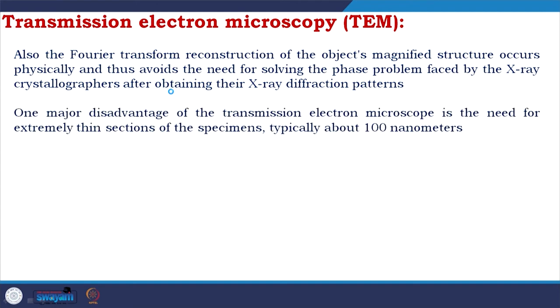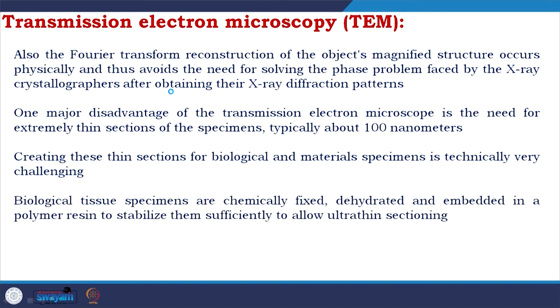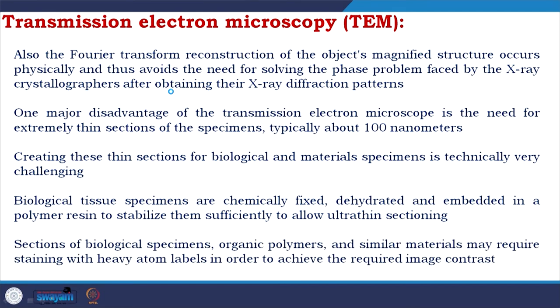One major disadvantage of TEM is the need for extremely thin sectioning of the specimen, typically about 100 nanometers — this is technically very challenging. Biological tissue specimens are chemically fixed, dehydrated, and embedded in a polymer resin to stabilize them sufficiently to allow ultra-thin sectioning. Sections of biological specimens may also require staining with heavy atom labels to achieve the required image contrast.